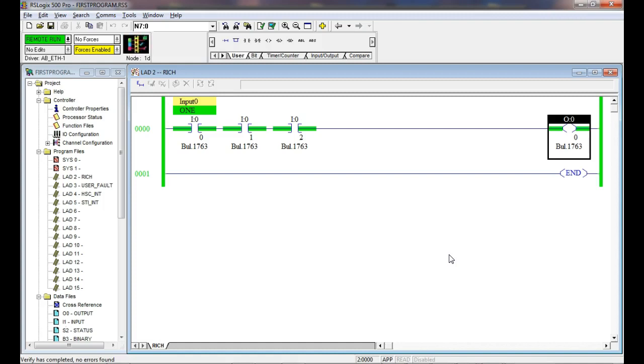So here we didn't have to supply a slot number. Why? Well, we did. It's just that on a fixed PLC, your slot is going to be 0. This is not a fixed PLC. This is a hybrid PLC. So what we can do is we can put another module over here. Your internal would still be 0, and then that module would be 1. Everybody understand that?